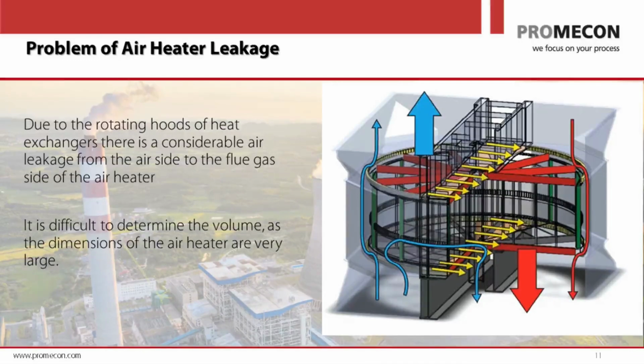Flue gas is coming down through the air heater and it's heating up the plates, and by that it's losing a lot of its thermal energy. So when the flue gas gets out, it's about 300 degrees Fahrenheit or even less. So these heated plates now slowly rotate into the other section of the air heater that you can see with this blue arrow, and the fresh air coming through is heated up by the plates. So the plates are basically pushing the heat back into the boiler by moving the heat from one side of the rotary air heater to the other side. And the cold air, which is basically the fresh air taken in by the FD fan, is then passing by these plates and picking up the heat.